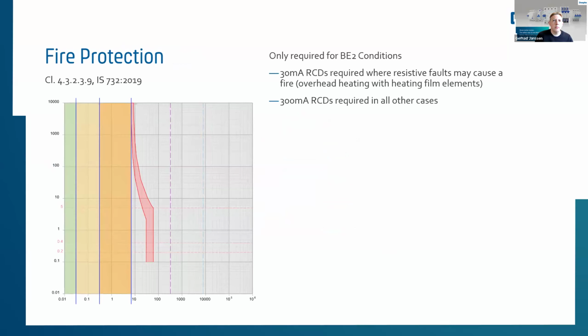The next slide is showing the possibility of an MCB. On the left side, you see the green, yellow, and orange part of it. So this whole part is covered by an RCD. So 30 milliamp RCDs are required where resistive faults may cause a fire, or 300 milliamp RCDs are required in all other cases. So with RCDs, you're able to prevent fires and also prevent electric shocks. If you take an MCB, for example, shown in this tripping curve here, it would not be able to give you fire or human protection. So an MCB is line protection and not, in the first case, fire and human protection.